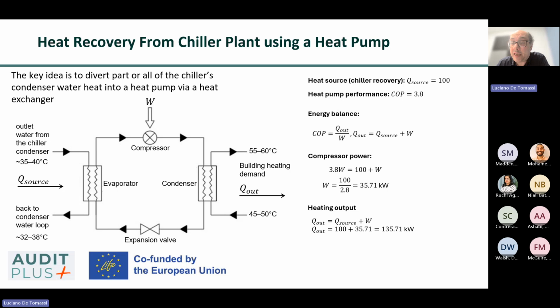In a conventional chiller plant, the condenser rejects heat into a circulating water loop. This loop leaves the chiller at around 35 to 40 degrees, and normally returns cooled water at approximately 32 to 38 after its rejection in cooling towers or dry coolers. When a heat pump is added, this condenser water loop becomes an available low temperature heat source.